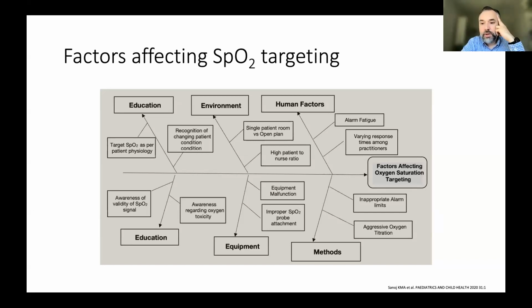Consider using the function of delaying the alarms. So if the value goes outside the range but only for a short period of time, we can set the device to a mode that won't alarm straight away, but will wait some seconds before it starts alarming. That can be helpful.